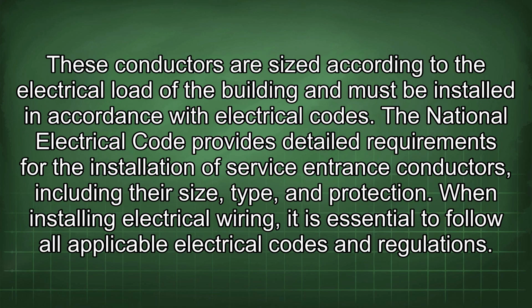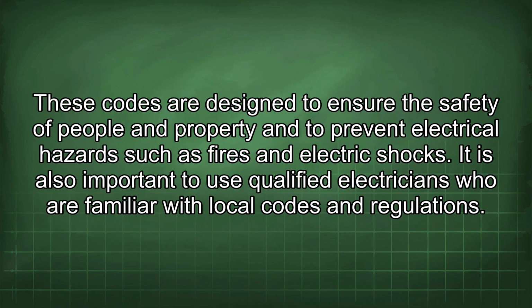These conductors are sized according to the electrical load of the building and must be installed in accordance with the electrical codes. The National Electrical Code provides detailed requirements for the installation of service entrance conductors, including their size, type, and protection. When installing electrical wiring, it is essential to follow all applicable electrical codes and regulations. These codes are designed to ensure the safety of people and property and to prevent electrical hazards such as fires and electric shocks. It is also important to use qualified electricians who are familiar with local codes and regulations.